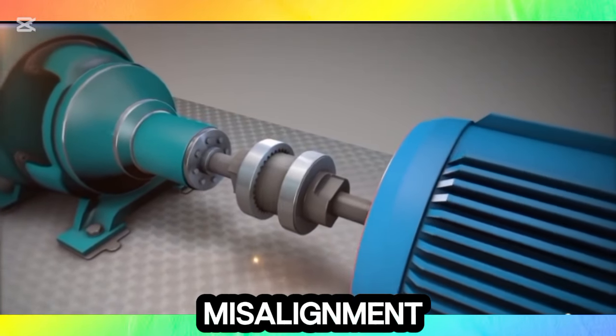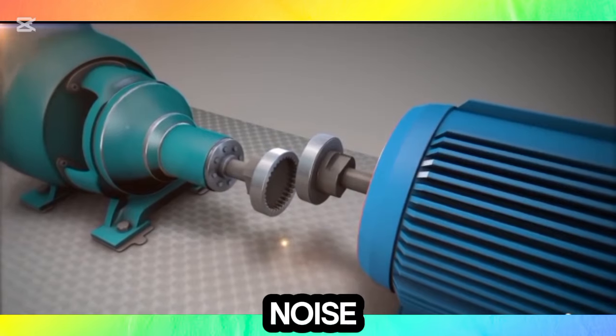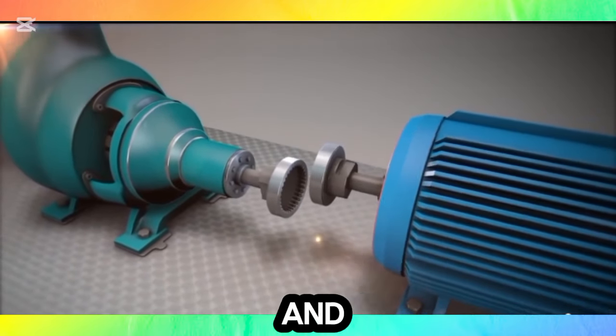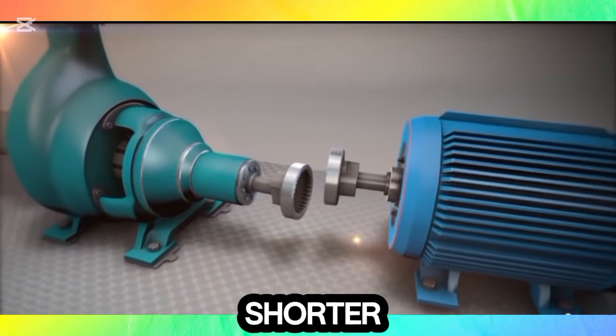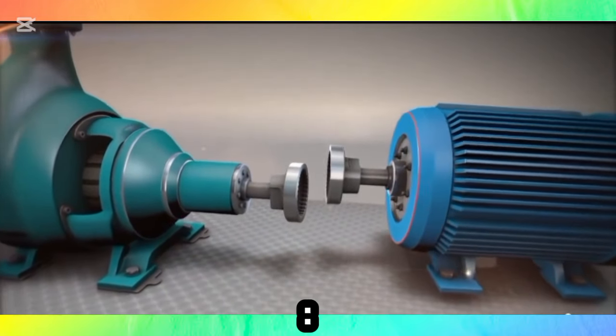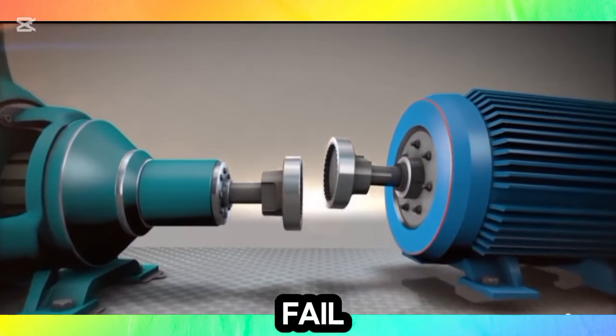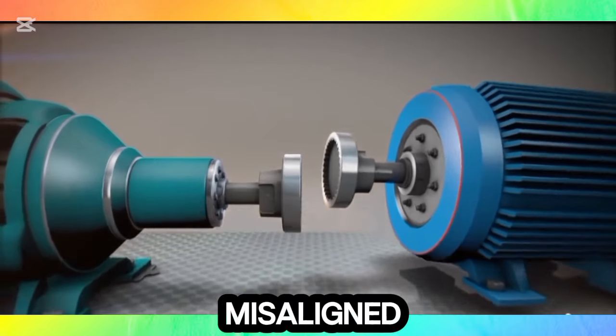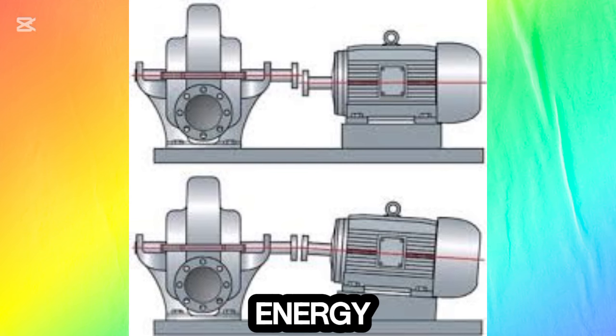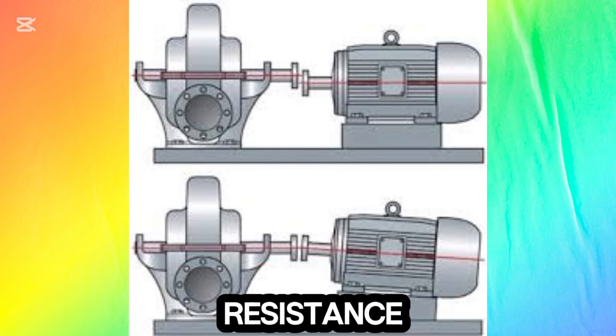Consequences of misalignment: increased vibration, leading to noise and reduced efficiency; bearing and seal damage, resulting in shorter equipment life; coupling wear. Misalignment can cause couplings to fail prematurely. Energy loss. Misaligned systems consume more energy due to increased friction and resistance.